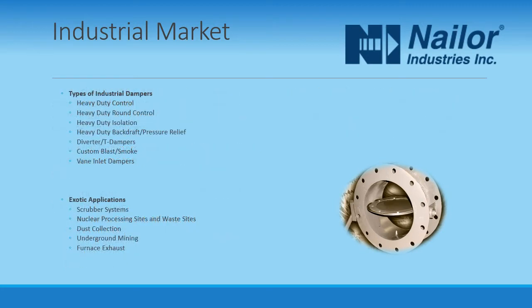Industrial dampers may be categorized generally by the type of function they are designed for. Here are some of the most common types: heavy-duty control dampers for process control; heavy-duty round control dampers, also used for process control, tending to be single blade or butterfly type; isolation dampers for sealing off ductwork for quality or safety; backdraft and pressure relief dampers for pressure control and to ensure one-directional airflow; diverter or T-dampers to split or redirect hot gas flow; blast and smoke dampers for life safety and blast control; and vane inlet dampers to pre-spin air entering a fan to economize fan operations.